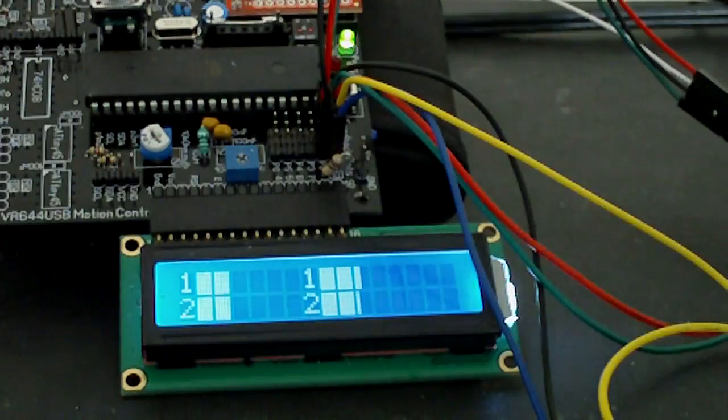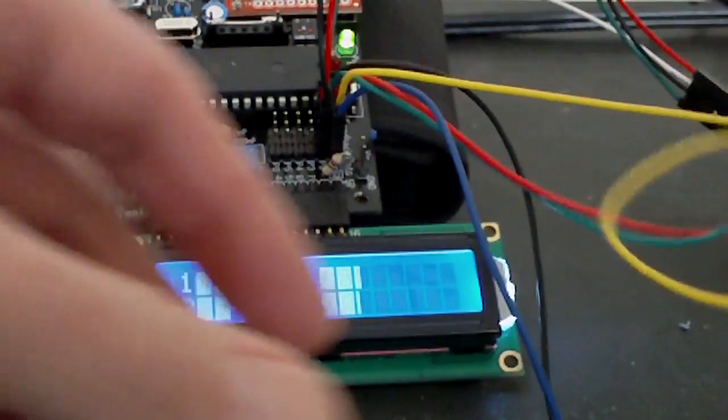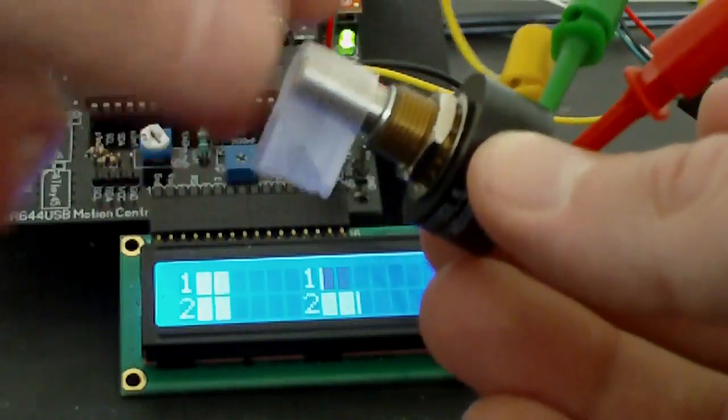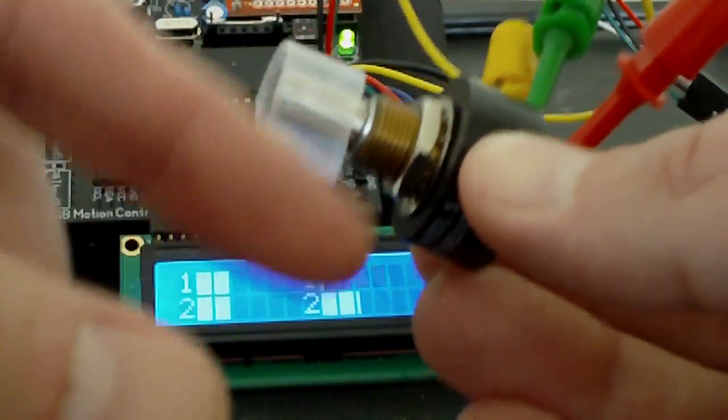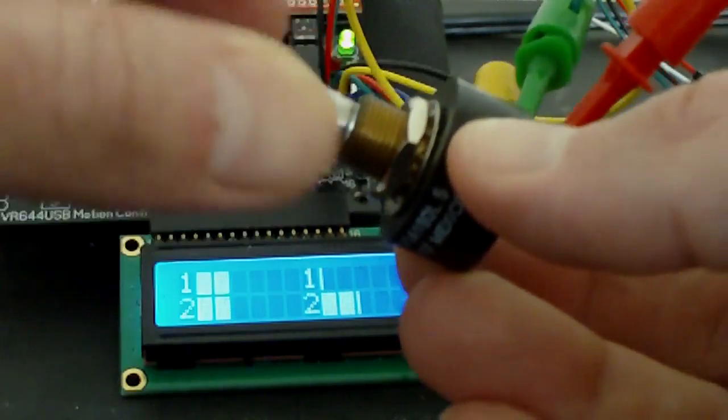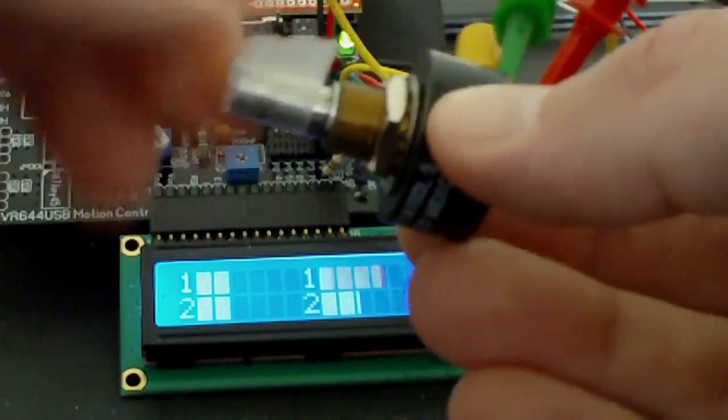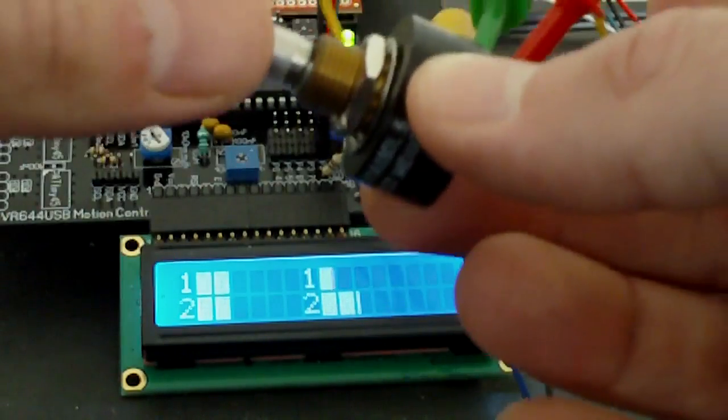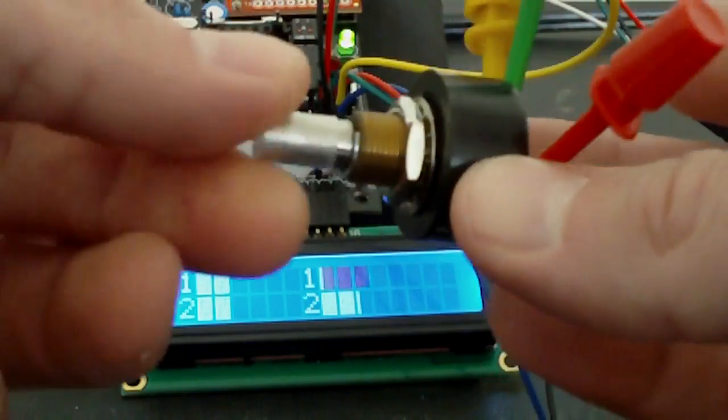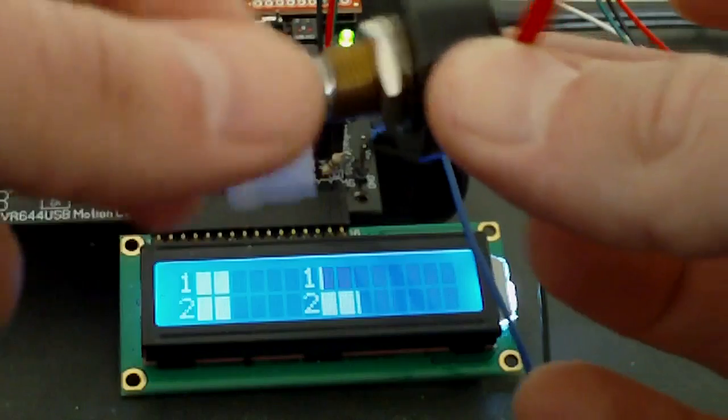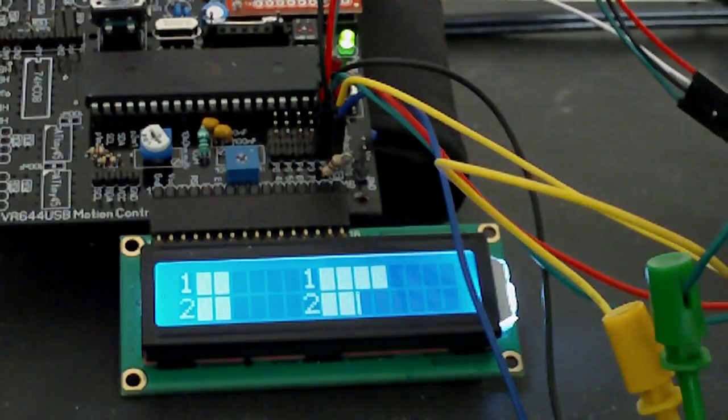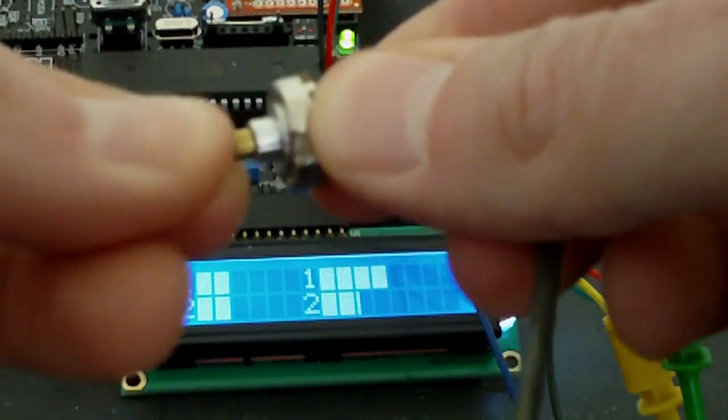Now I'll show it to you here. I have to disconnect it from the AMC. Now you'll see that this sensor doesn't have hard limits, which means that you can turn it, turn it, turn it. It doesn't find a stop position like the other ones - for example, this one here has a hard stop.